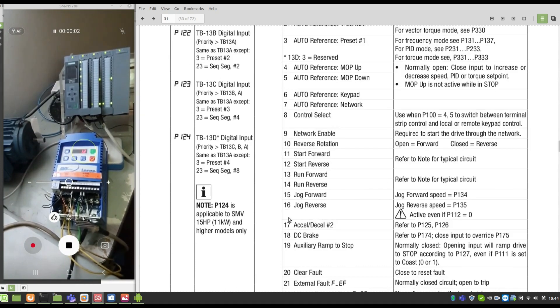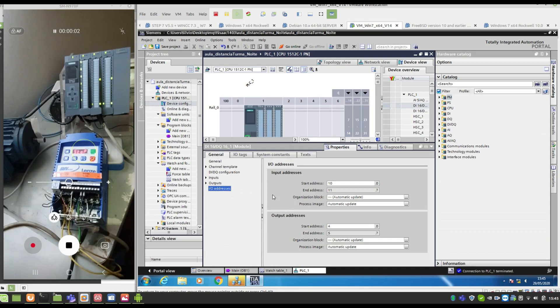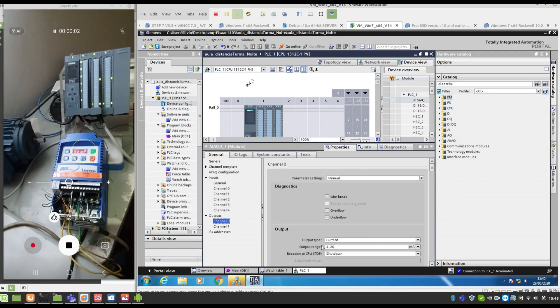Now we're going to the PLC. As you can see here, we have the PLC CPU 1512C. It's a very good one with integrated inputs — 32 digital inputs and 32 digital outputs, 5 analog inputs and 2 analog outputs. We're going to use three terminal outputs: Q4.0, Q4.1, and Q4.2. The analog outputs are very important to configure — you must define it to 4 to 20 milliamps.